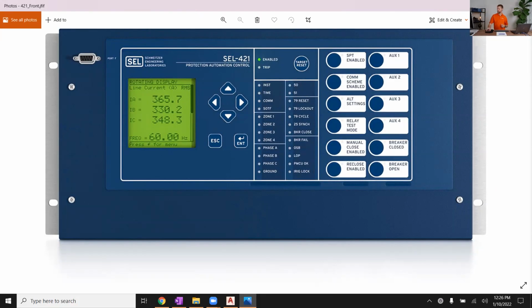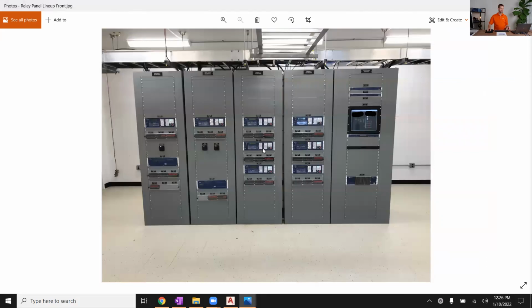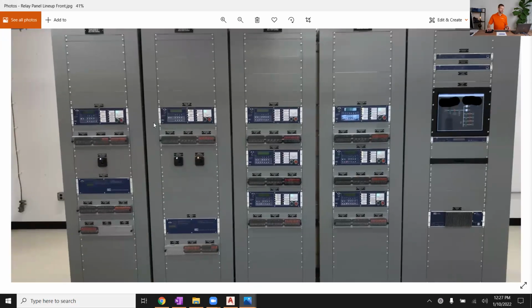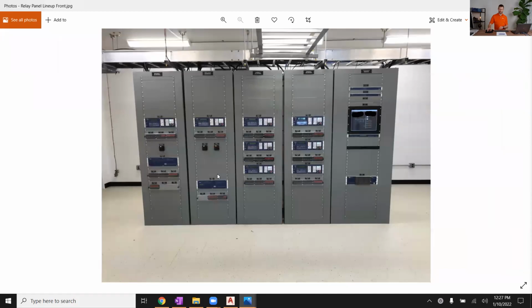Some of you may or may not be aware of where these relays go in the protection system. If that's you, I've got an image that will give you some more visual understanding of that. This is a relay panel lineup in a substation control house. This happens to be a distribution substation, a somewhat smaller lineup, but in each of these, we've got a number of relays in a panel. We've got test switches, which we're going to talk about in this course. We've got some lockout relays, which we're going to talk about. We've got some control switches, etc. All of this is mounted inside of this relay panel inside our house.